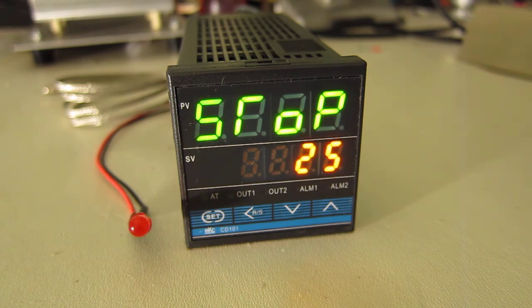I'm not sure why it's continuing to cycle the outputs but my understanding is that in this mode the output should be off. The reason this might be an issue is that if you have this PID controller connected to something like a solid state relay controlling say a heater, ideally what you'd like to be able to do is put the controller into stop mode and the heater would stop operating.